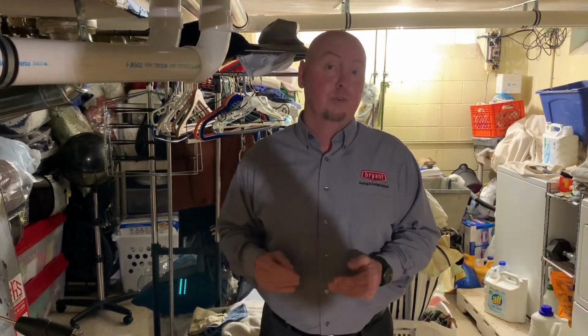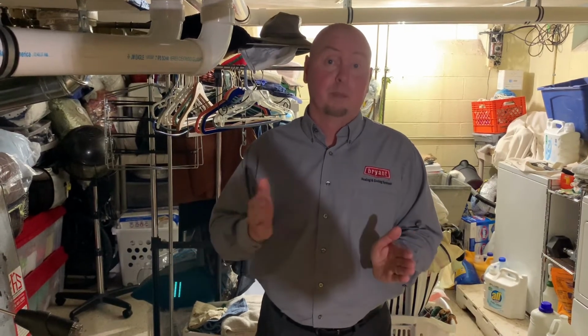What you really got to watch for is low O2. When that number starts going under 5%, 4%, 3%, that indicates something is probably not right. You're not going to have enough oxygen for combustion. And most importantly, look for that number upon startup, and then see if there's a difference when the blower comes on.